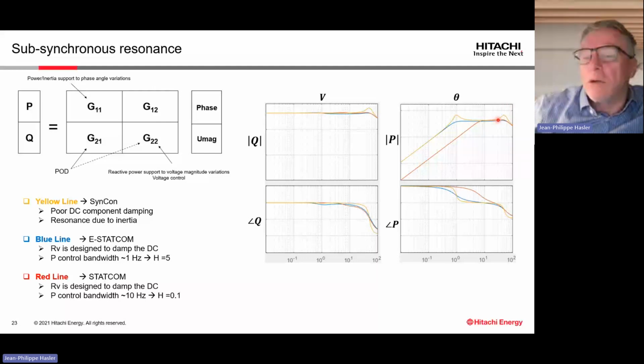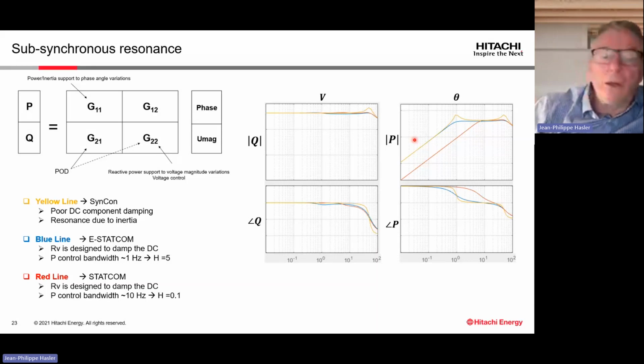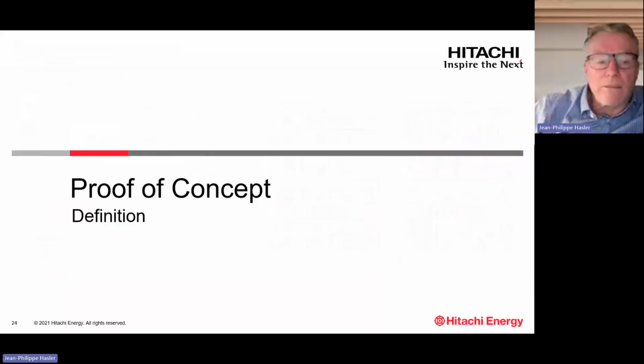We see that in the E-STATCOM or STATCOM mode, we try to damp the DC very fast. That means we don't have any resonance. But in the case of a machine, you will get a resonance at 50 Hertz or close to it, and that gives this sometimes very poorly damped oscillation during some transients.